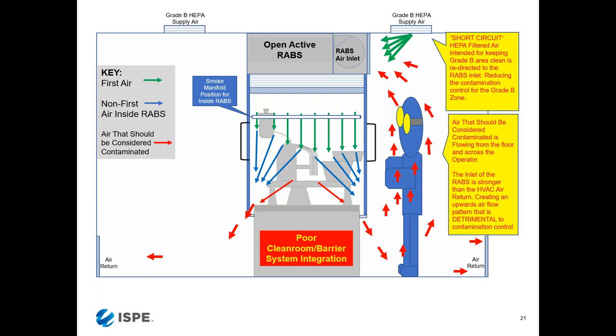What is happening? The air comes down, it goes over the operator onto the inlet grill of the RABS. Isn't the operator sacred here? Because this is the operator who will be opening the door, and floors are dirty or clean - they're dirty. So you see this air is coming down, lifting the dirt over the operator into the inlet grid. And what is he doing? What is this air doing? It's contaminating the operator. That is why we see so many 483s and some data integrity issues, because we don't understand this concept.